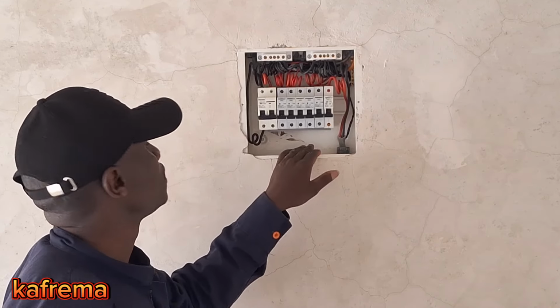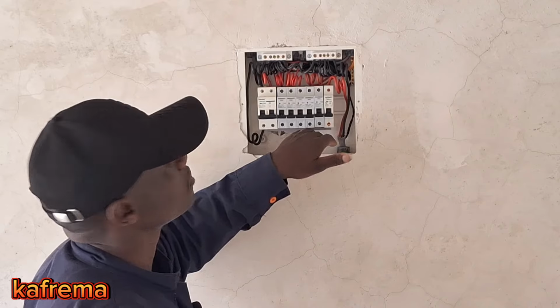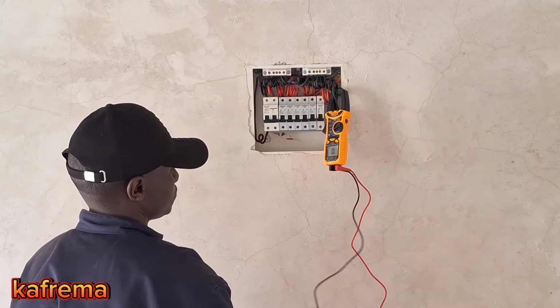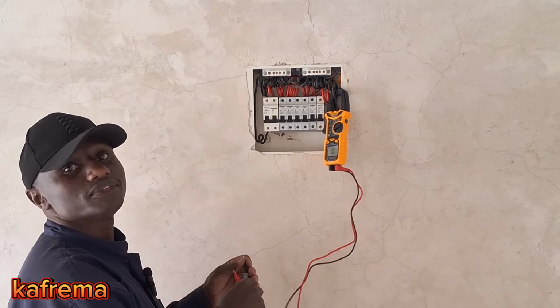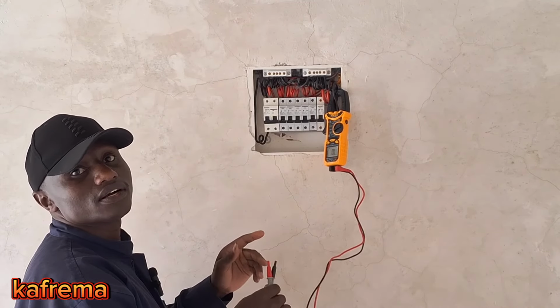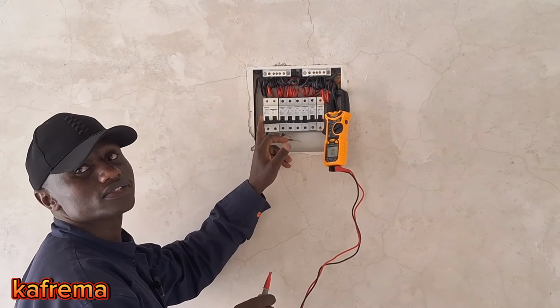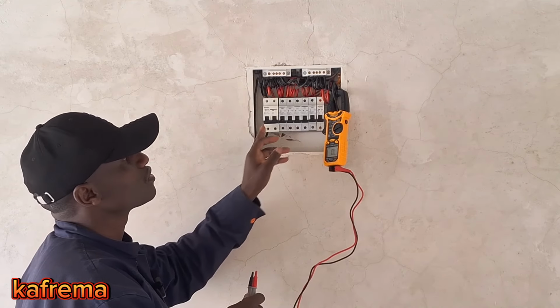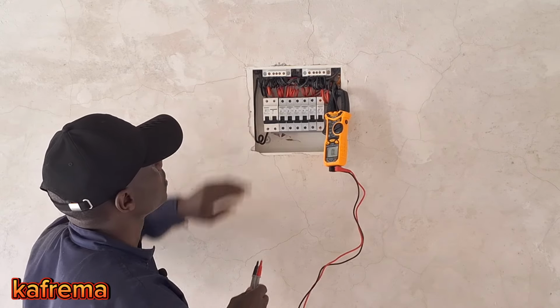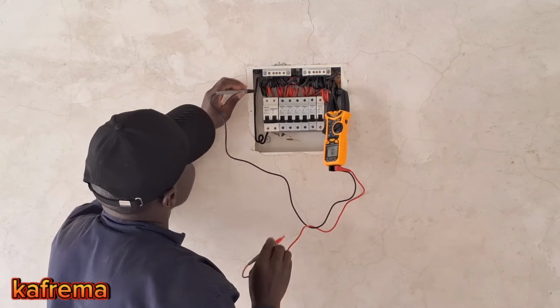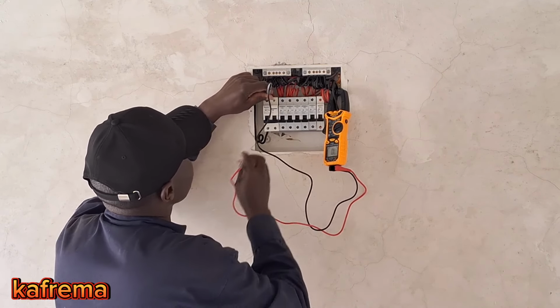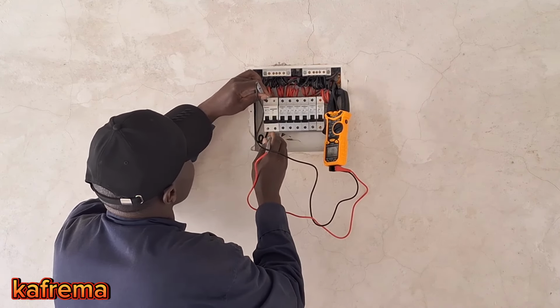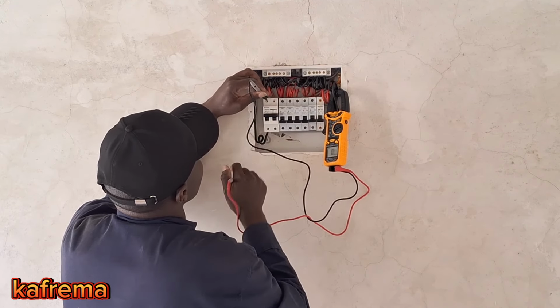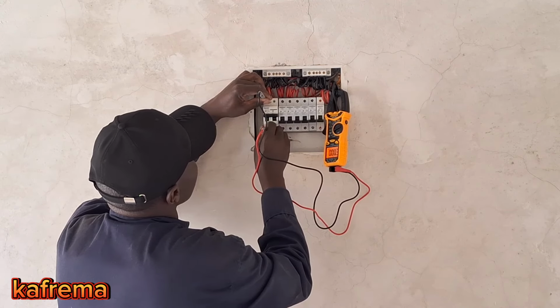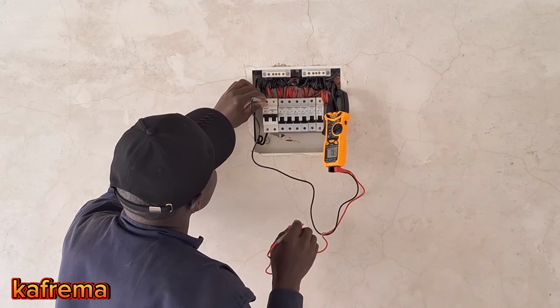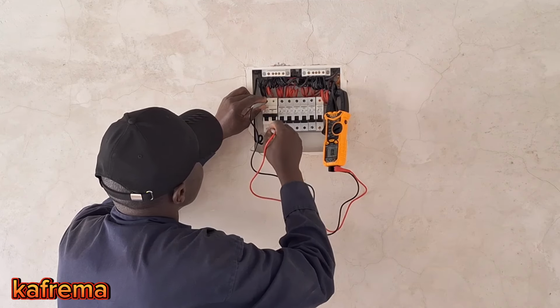I'm going to do a continuity test. Let me get the meter. Guys, we can do some tests here to see whether our wiring is correct or there is an open circuit, not on the main but on this consumer unit only. So we know this way we have closed or we have opened the circuit, so there should be no short. And when we put it on, from the source we can get the continuity of the neutral.